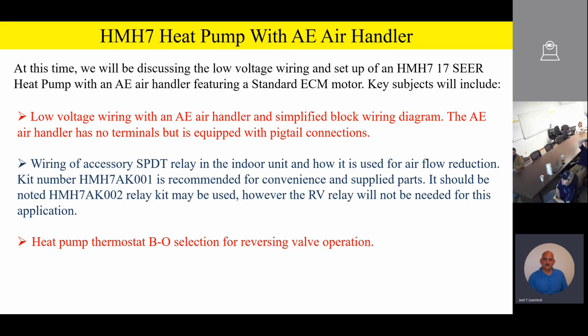Now, it should be noted that there's another kit, a 002 relay kit, and that's going to be for variable speed products. So the HMH7AK002 kit is going to be for variable speed products. However, the only difference between the 001 and the 002 kit is the 002 kit has 2 relays instead of just 1 relay. That's how you know the difference between them. The 1 means it's just 1 relay on the little board. The 2 means there's 2 relays on the board.